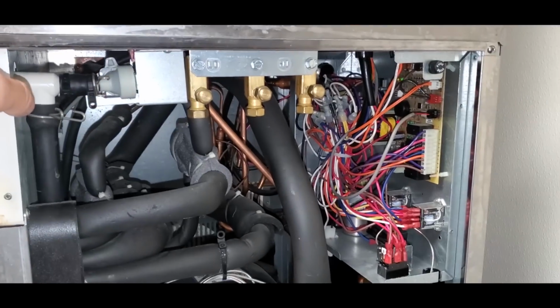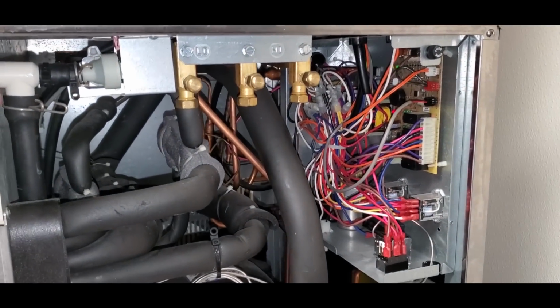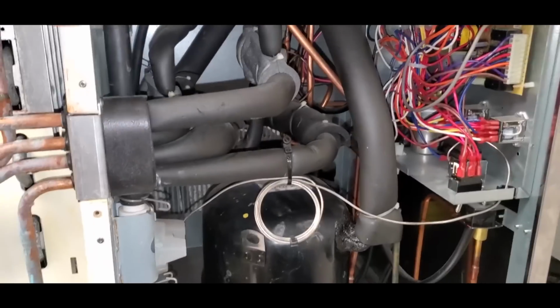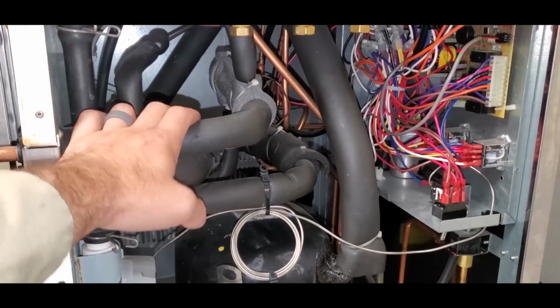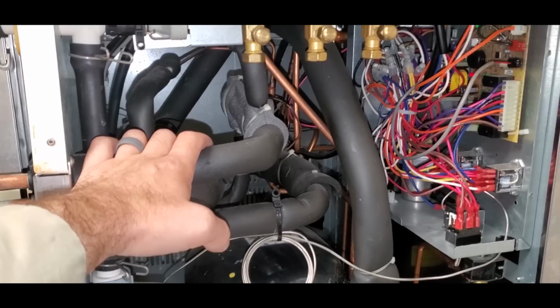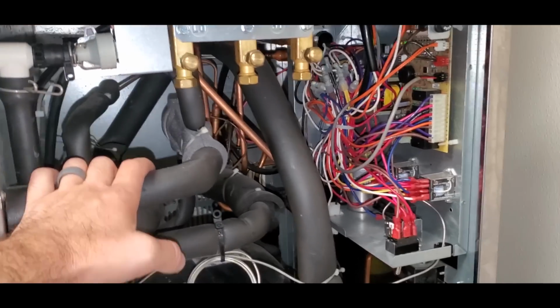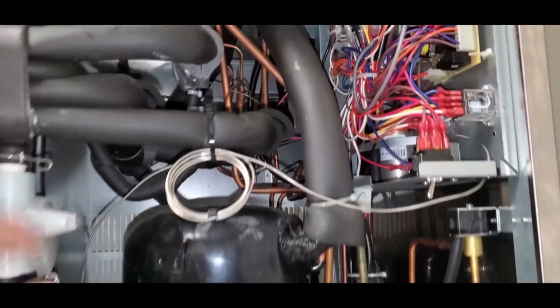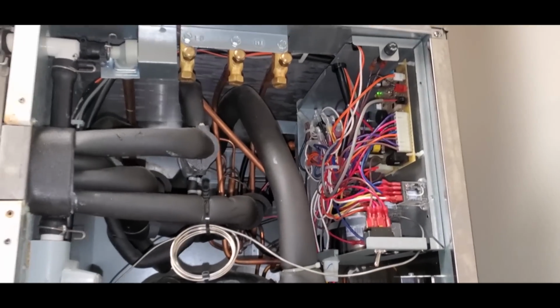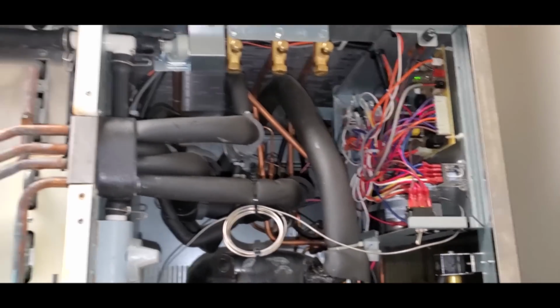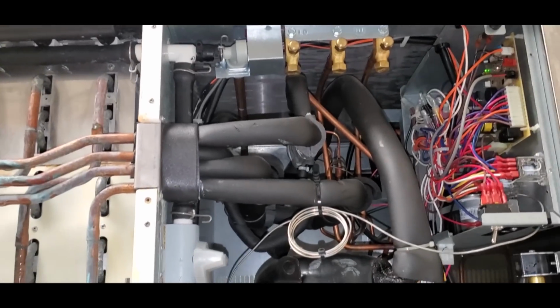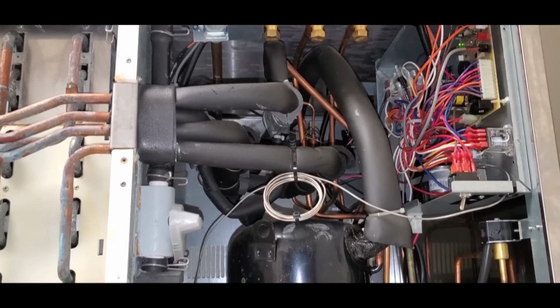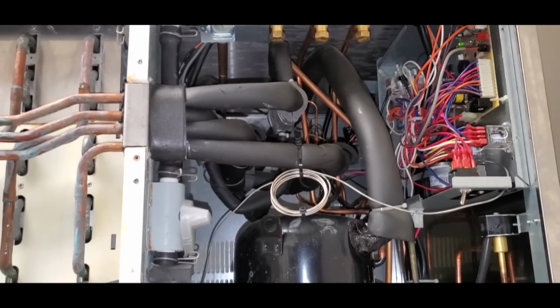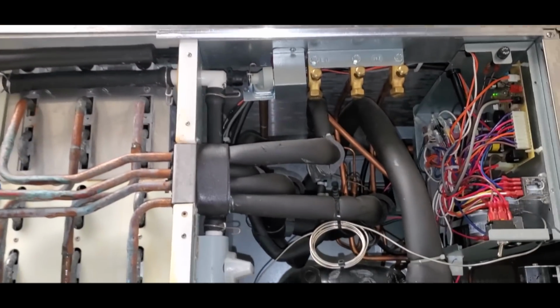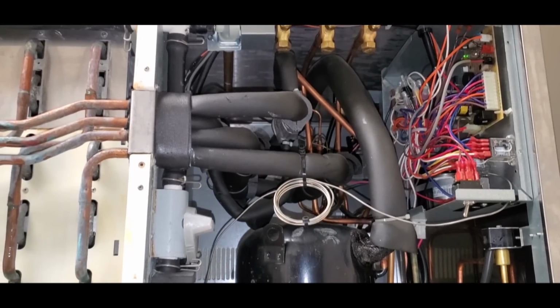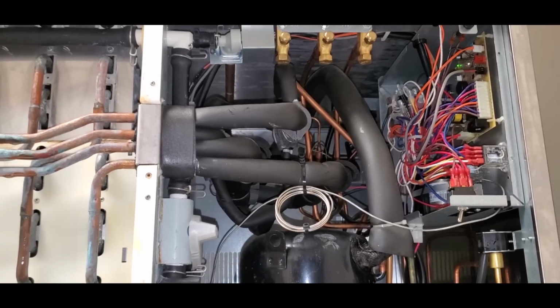And they're saying they're only hearing one beep. So, you know, it's a possibility that it could be a thermistor or a hot gas valve stuck on. But if that was the case, I would think it would be happening during the day too. And they said it's been happening for a couple weeks now, and it only happens first thing in the morning. A single beep is high evaporator temperature, which makes me think that they have hot water going to the machine. But right now there's not hot water, it's 72 degrees. But it just makes me wonder at nighttime if they're getting hot water to this machine.